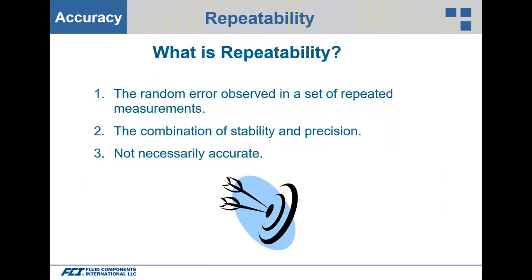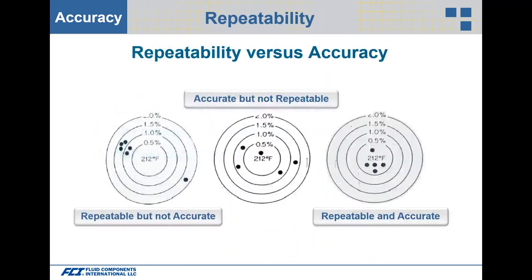What is repeatability? Repeatability is part of accuracy — the random error observed in a set of repeated measurements, the combination of stability and precision, not necessarily attributed to accuracy. Looking at repeatability versus accuracy: on the left-hand side you see dots that are relatively close together — we'd call that repeatable, but it's not accurate, because none of the dots are in the bullseye.